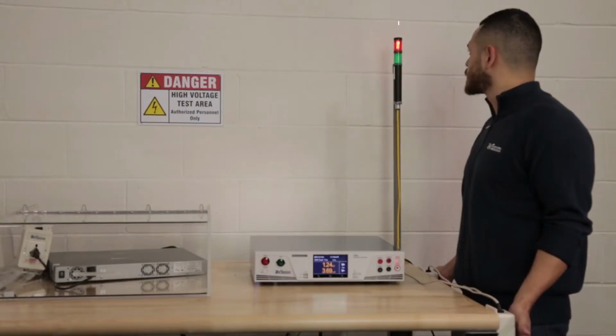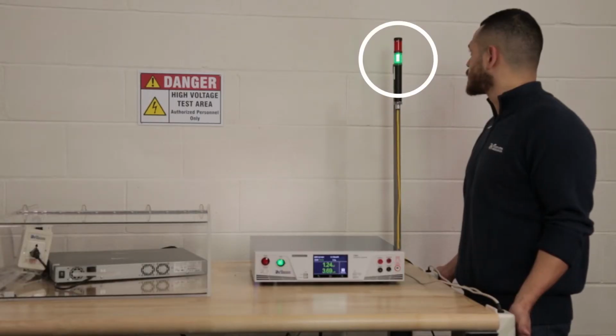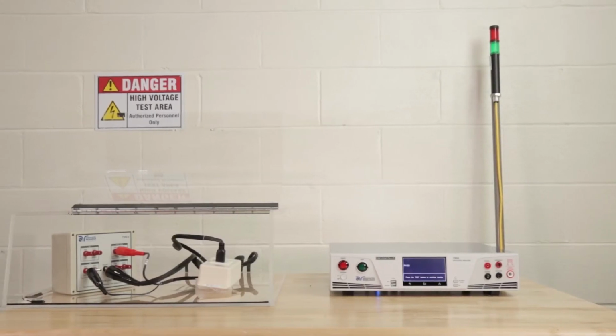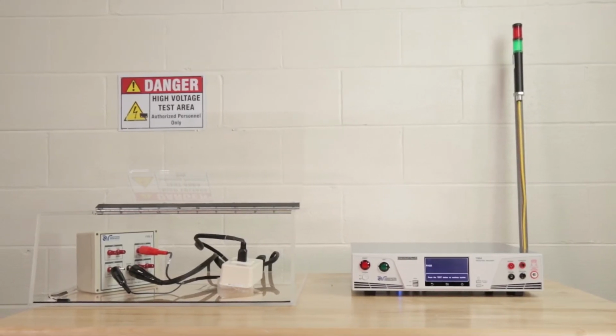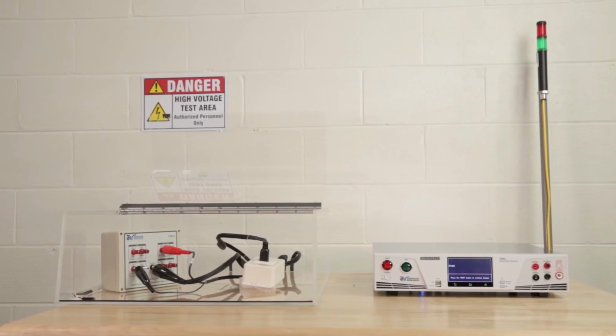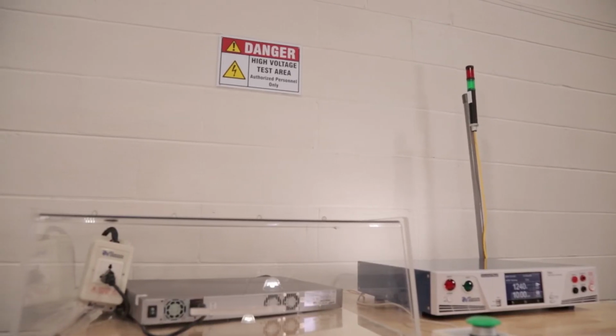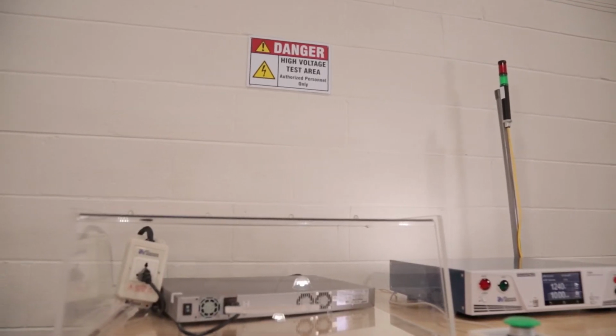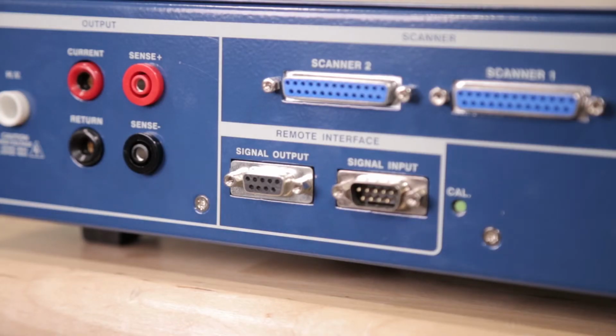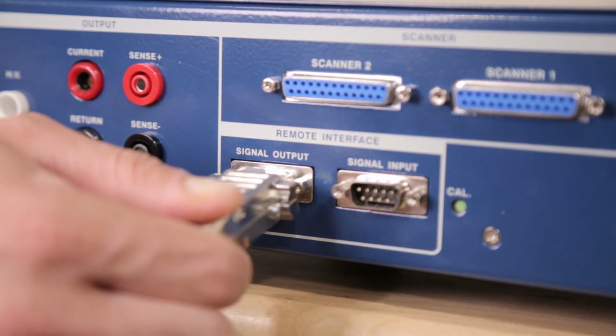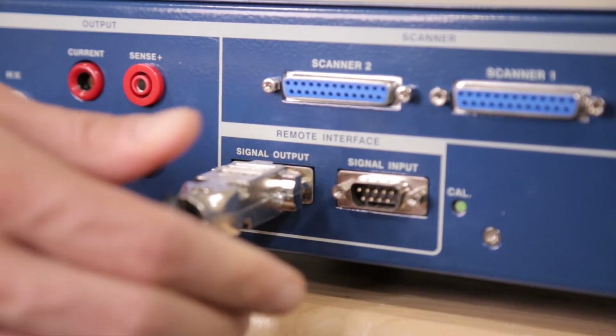Our signal tower light, as part of a safe workstation, provides a clear visual indication of test status to both test operators and bystanders. The tower light must be installed in an elevated position, so it's visible even at a distance. To connect, plug the 9-pin connector of the signal tower light into the signal output port of the rear panel of your instrument.